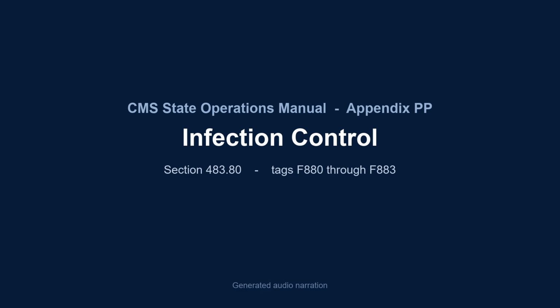Blood glucose meters. Blood glucose meters can become contaminated with blood, and if used for multiple residents, must be cleaned and disinfected after each use, according to manufacturers' instructions for multi-patient use. Additionally, staff must not carry blood glucose meters in pockets. The FDA has released guidance for manufacturers regarding appropriate products and procedures for cleaning and disinfection of blood glucose meters.